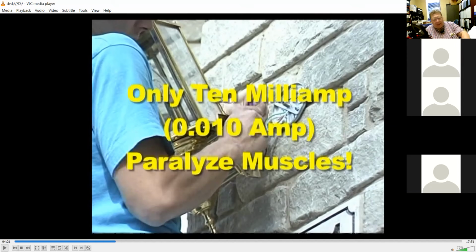Now, inside of the GFCI, what you have is a very small version of this. There literally is a current pickup coil inside the GFCI receptacle. If you read the paperwork on these things, next time you get one or when you come to school, we can show you the paperwork on one. They tell you that inside there's a small current pickup coil. Here's what it does. They take the hot wire and the neutral wire, both of them, and run them through a current pickup coil like this. Both of them.